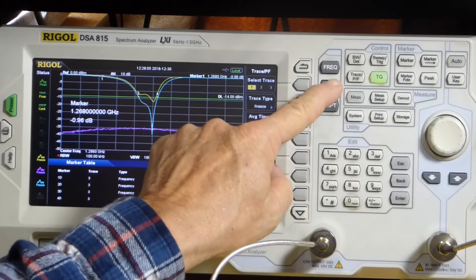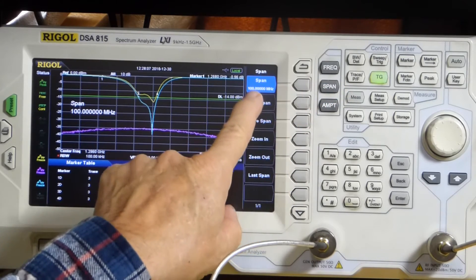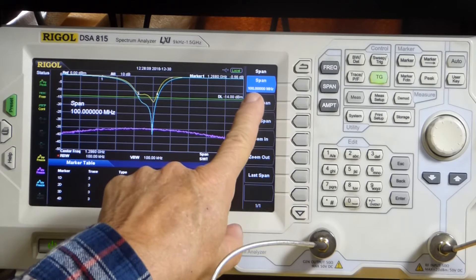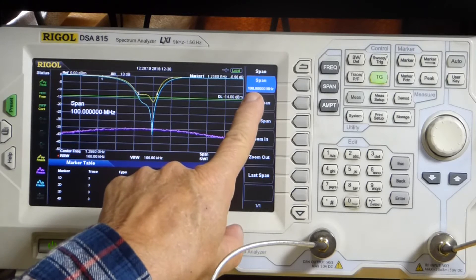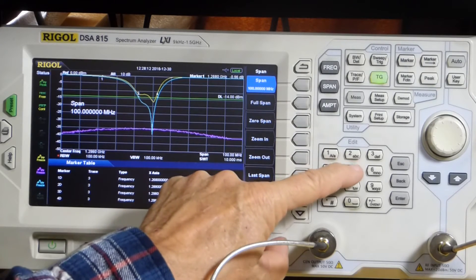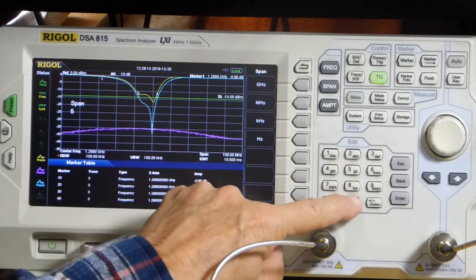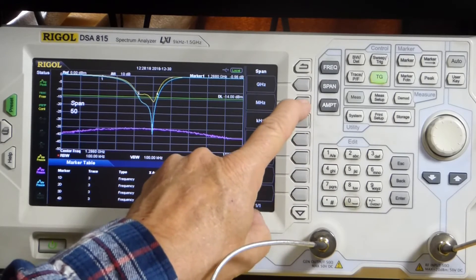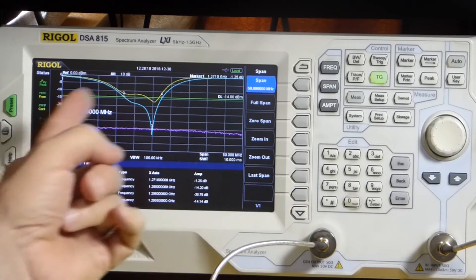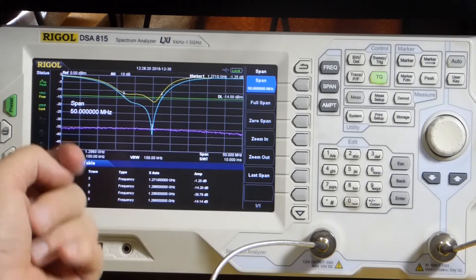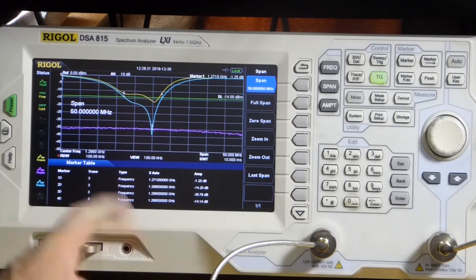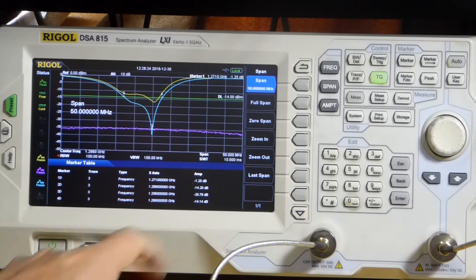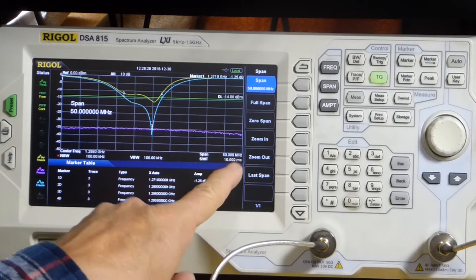As an example, I'll hit Span here. I'm at 100 MHz, as you see. Let's make that 50 MHz. 5, 0, MHz. And you see it expanded out to 50 MHz total. The span is 50 MHz.